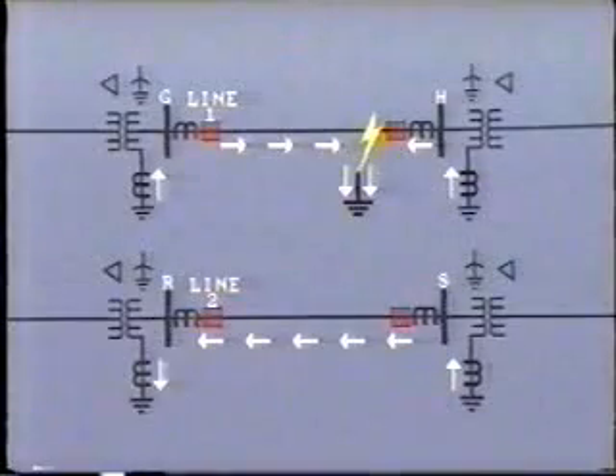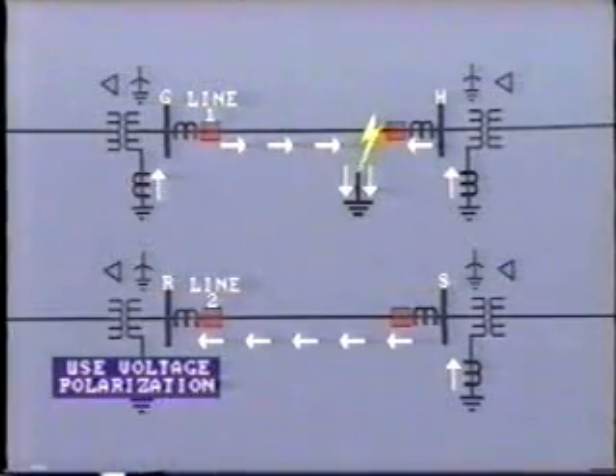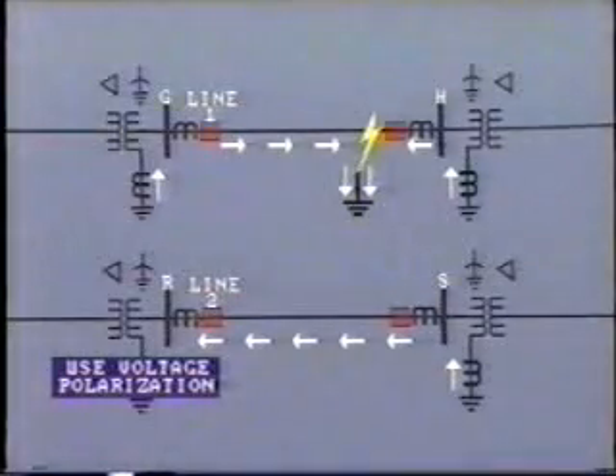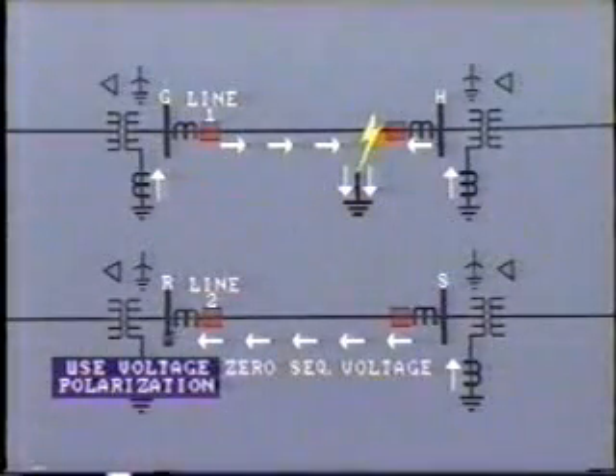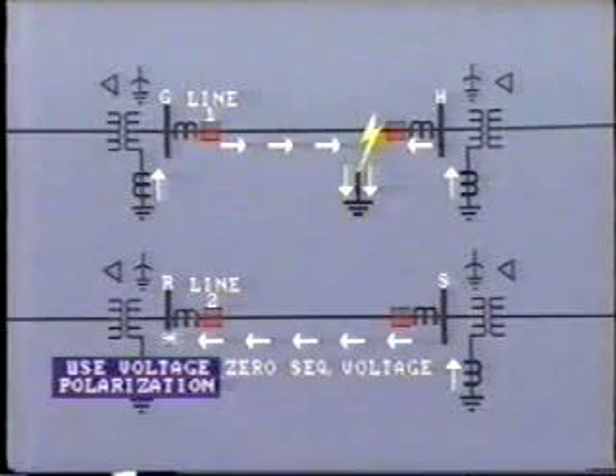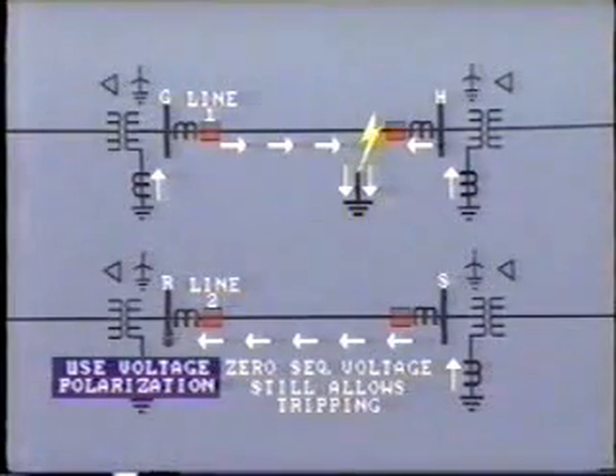The problem at bus R is the reverse direction of current in the neutral to ground. Perhaps the directional elements would operate better if we had voltage polarization instead. However, if zero-sequence voltage was measured and used at this point, it would still allow tripping, because zero-sequence voltage would be induced into the second line.